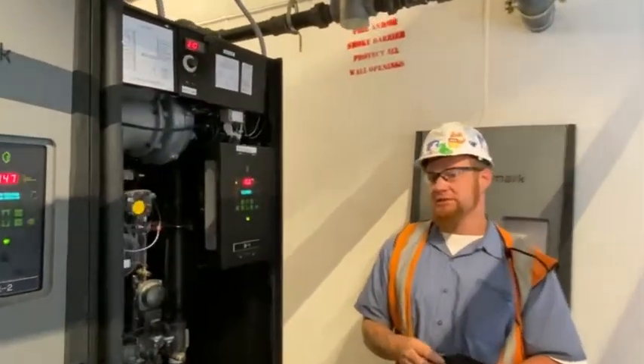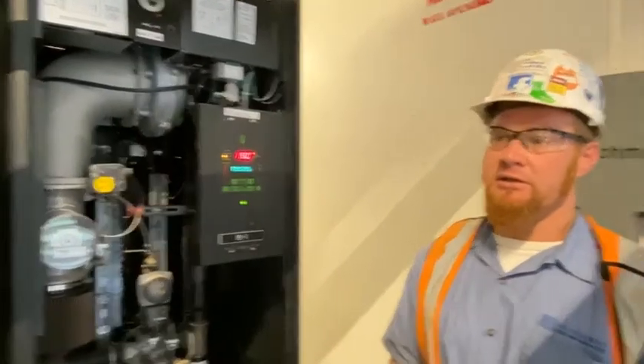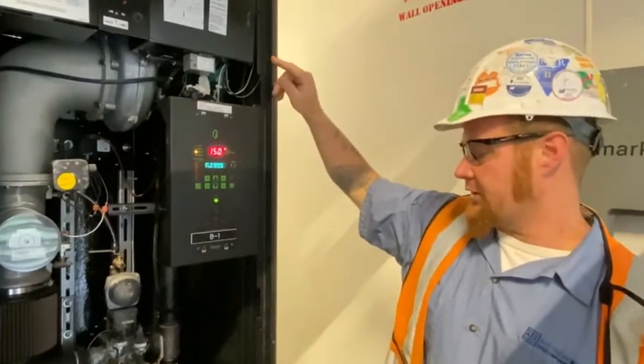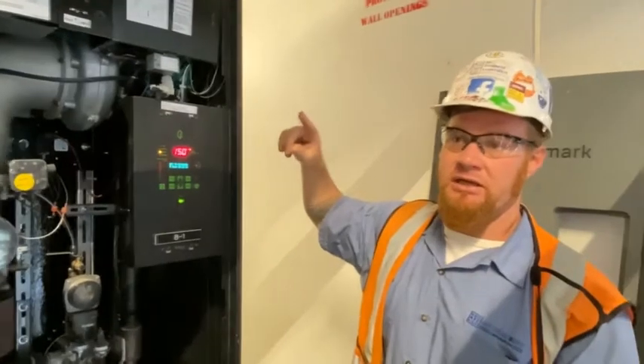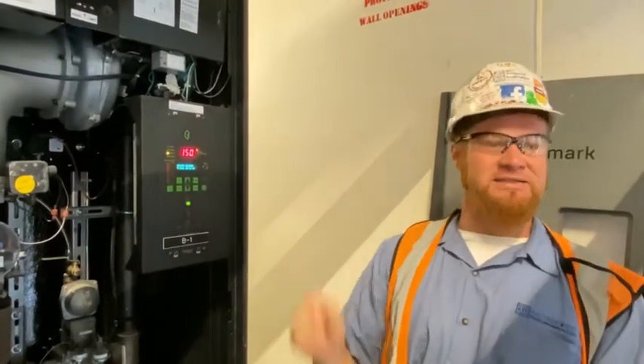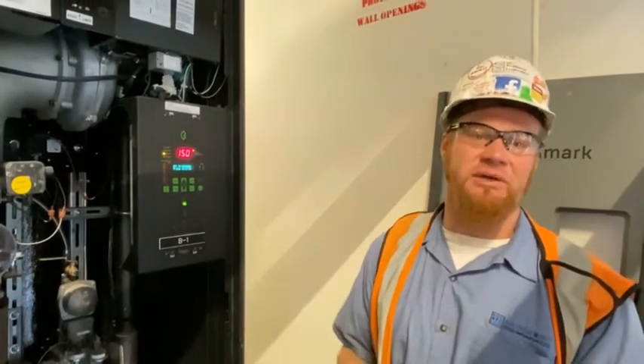There are two different maintenance options. When you contact AERCO for maintenance kits, there's a 12-month kit which includes flame sensors and spark igniter — that's your annual inspection. The second year, they have a 24-month maintenance kit which includes the gaskets to pull off the blower, inspect the burner sock, and a bit more thorough work. Every two years they recommend doing that, and then you go back to the one-year maintenance kit.